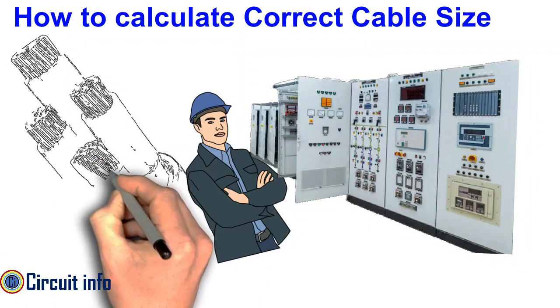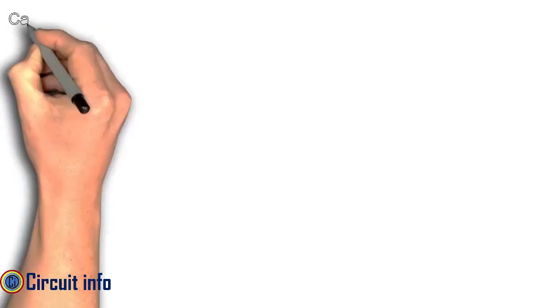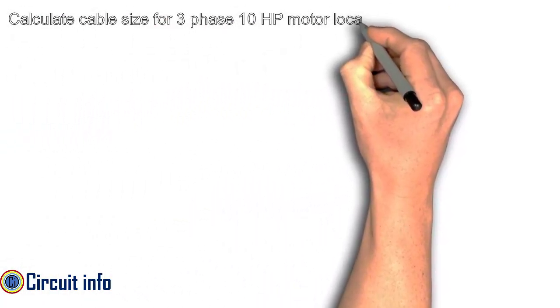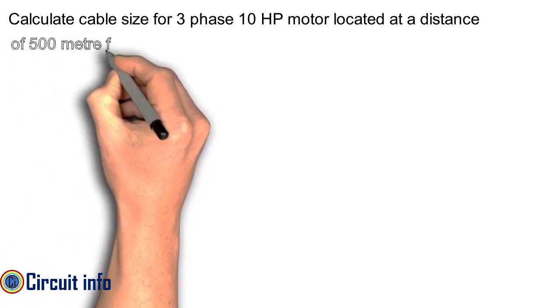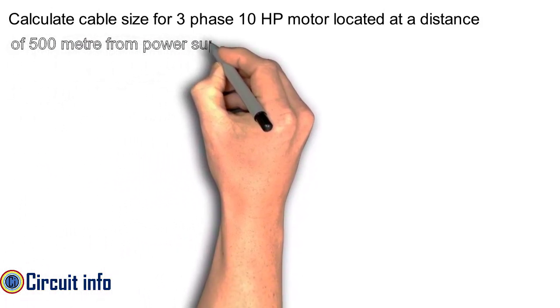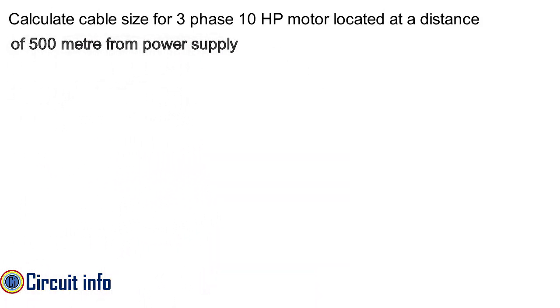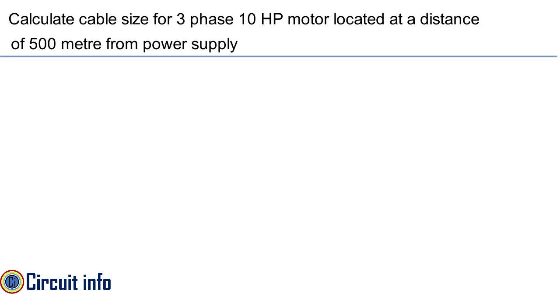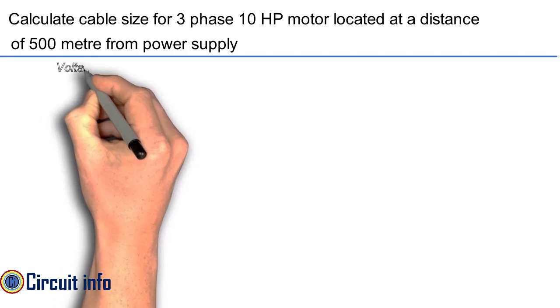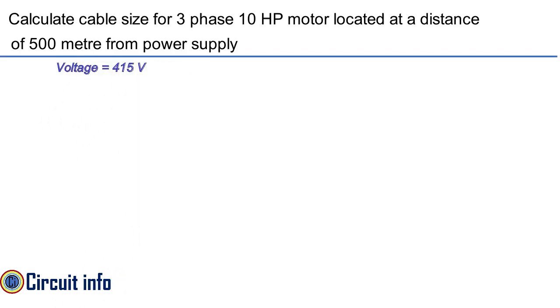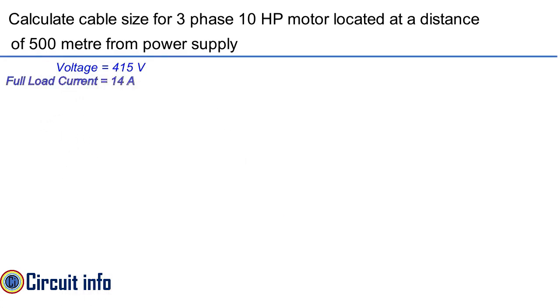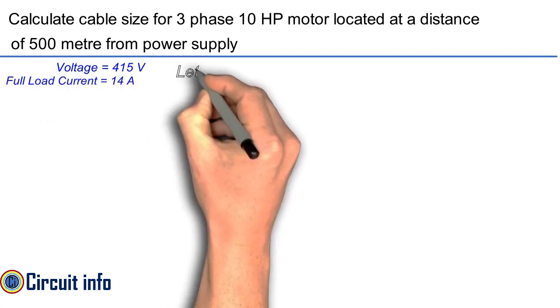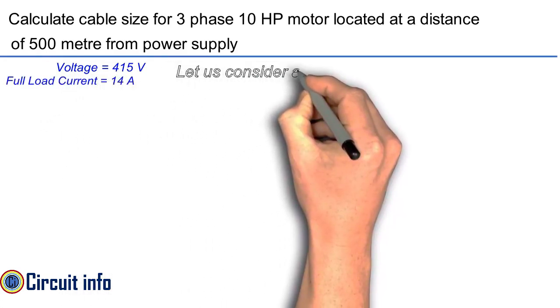We take one example: a 10HP motor located at a distance of 500 meters from the power supply. The supply voltage is 415 volt, the motor full load current is 14 ampere. Let us consider a three-core 16 square mm cable.